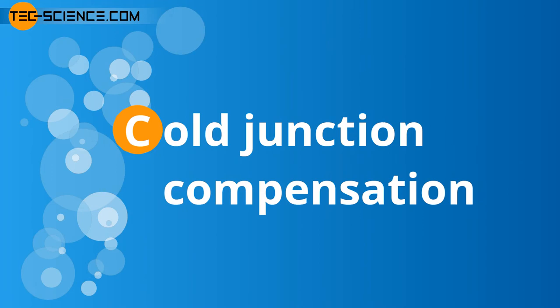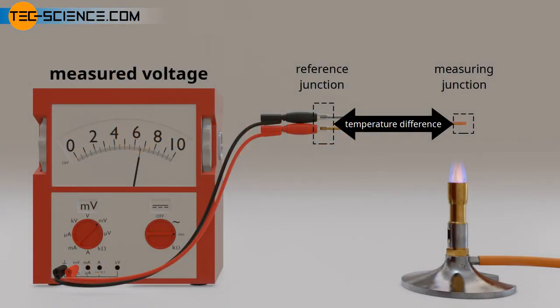Cold Junction Compensation. With the measurement setup described so far, only the temperature difference between the measuring junction and the reference junction can be determined with the measured voltage. To determine the absolute temperature at the measuring point, the temperature at the reference junction must therefore be known. This determination of the temperature at the reference junction, which is also called cold junction, is referred to as cold junction compensation.